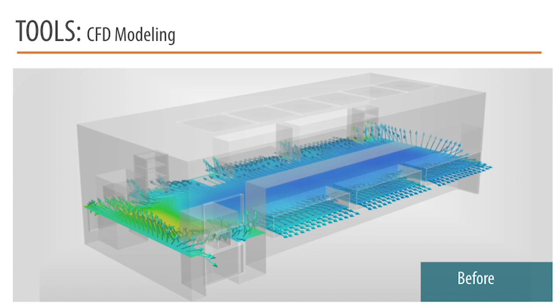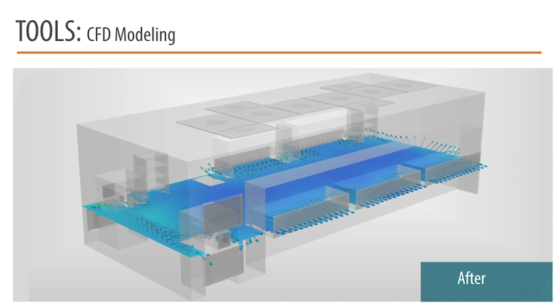The blue represents local mean age, how long the air is kicking around before it leaves the space through these sidewall returns. The blue was good, this was a little slower, and we were having trouble with certification down here. On the next slide, we did a number of iterations, added a few more 2x4 HEPAs pushing more air in selective places. We tried different placements, added more return chase, and vastly improved this end of the cleanroom, and it passed certification. Very powerful tool, and this proved out that the tool works.